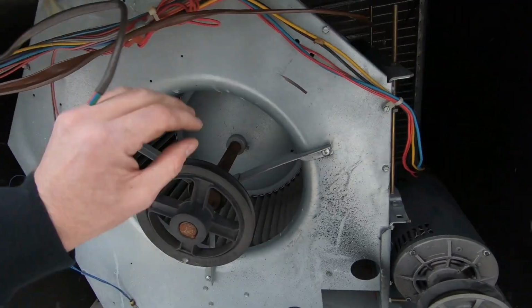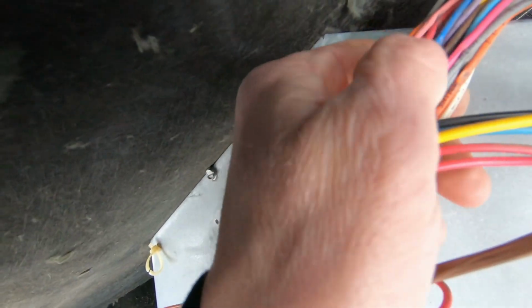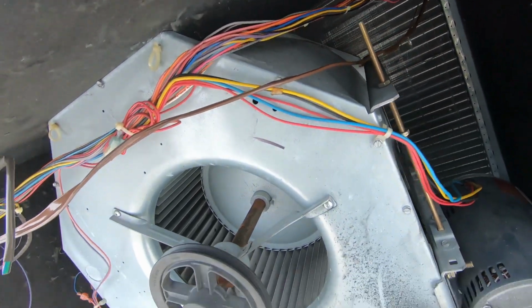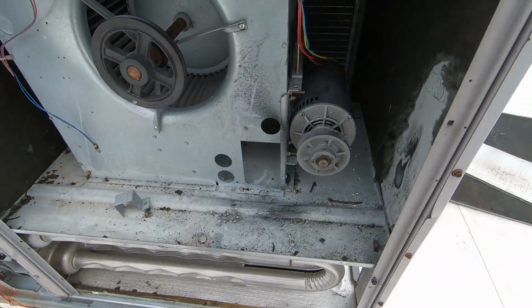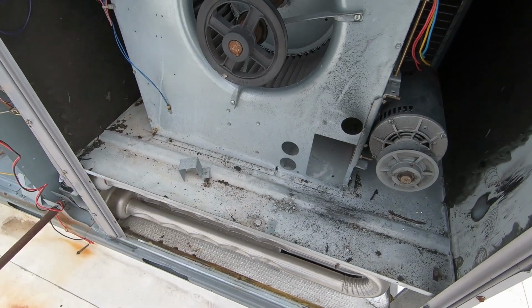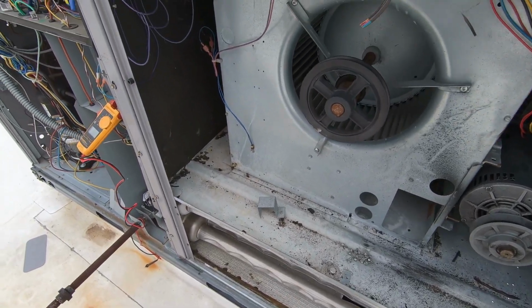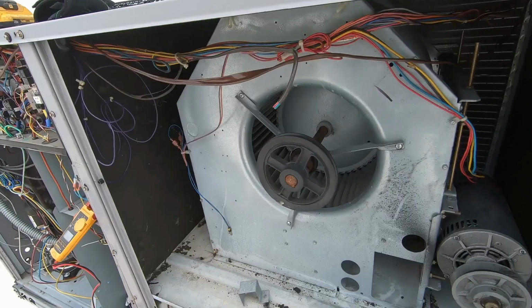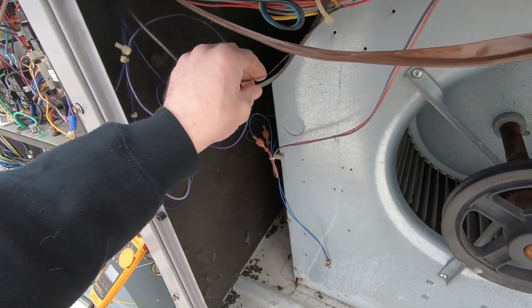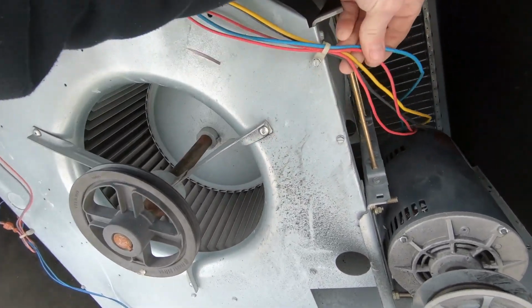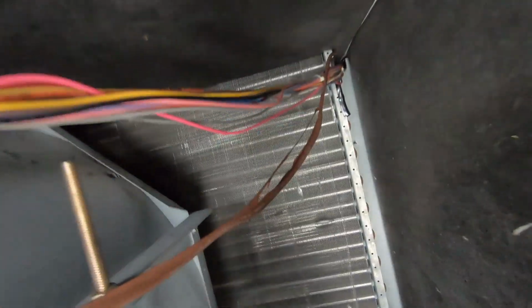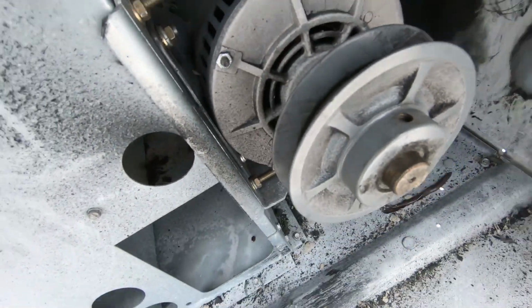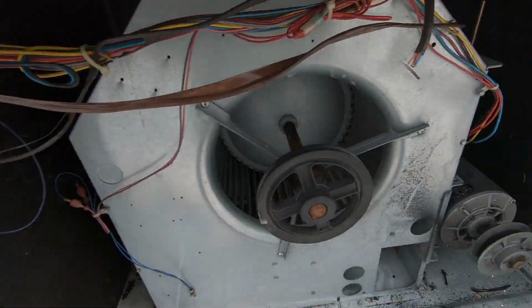All right, so the wires aren't rubbed out, but they certainly got hot enough that it's like melted. You can see all these wires got the indentation of the corner of the blower housing here. Belt came off, limit switch, high limit switch bypassed. This unit never stopped firing. We're gonna need to go through this and just confirm that all the wiring is good. Strictly from the heat, I can see melted wires back here. The motor smells burnt. The windings do have continuity, but just listen to it.